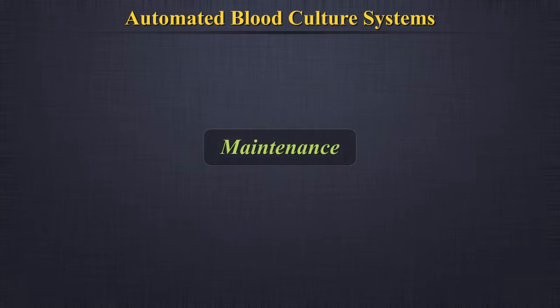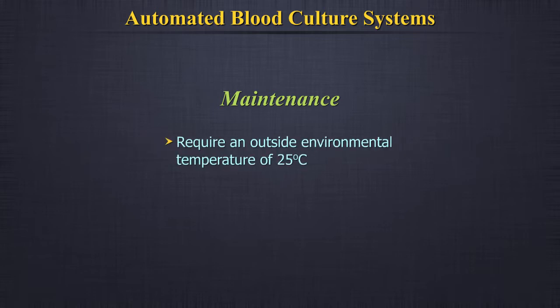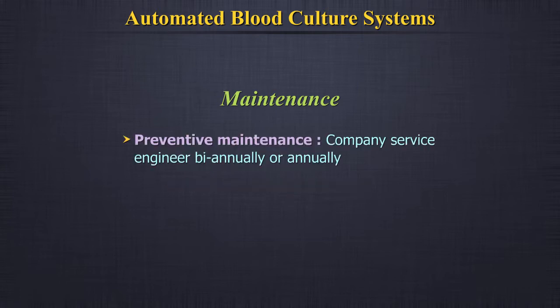Maintenance. Maintenance and calibration of automated blood culture platforms is strictly as per the manufacturer's instructions or operator manuals provided at the time of installation. Most of these systems require little maintenance from the user to provide reliable performance. All these instruments continuously work, require an outside environmental temperature of 25 degrees centigrade, and continuous UPS power supply. Apart from this, preventive maintenance is done by a company service engineer biannually or annually.